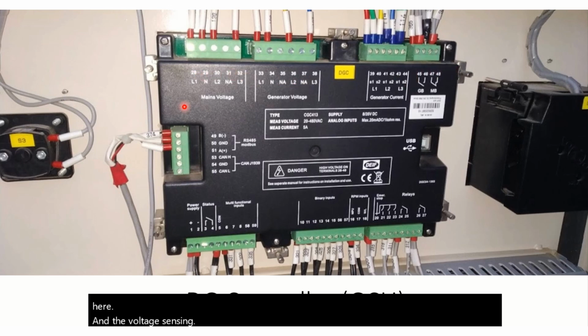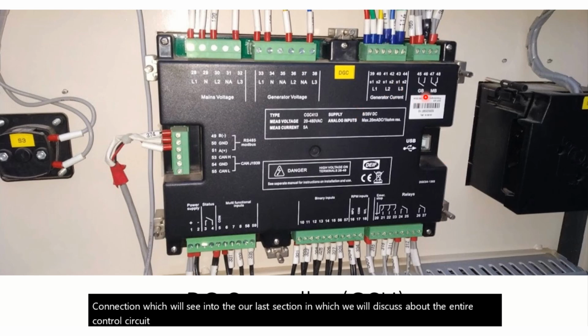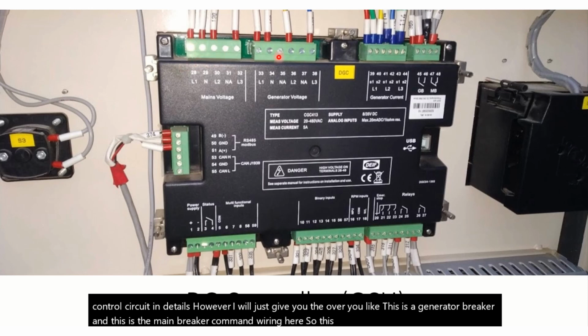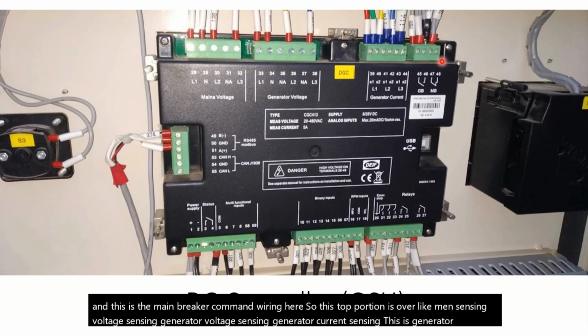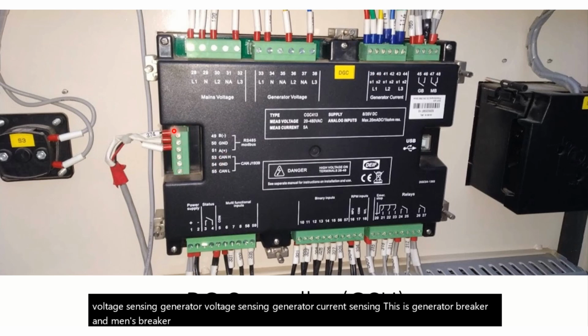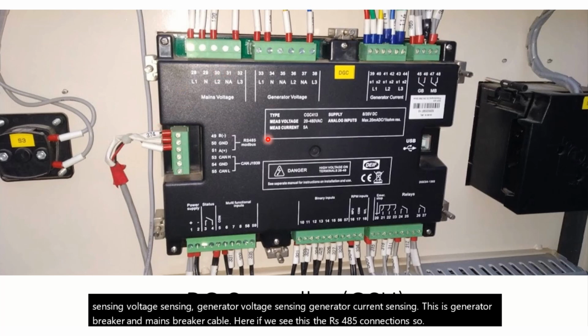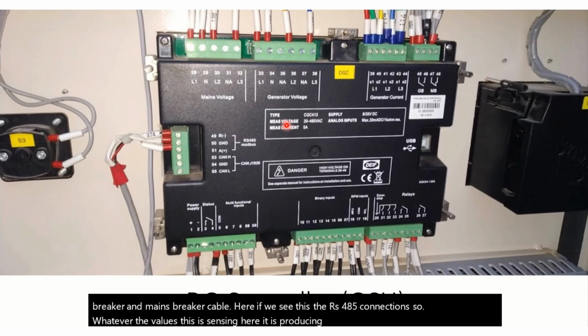These are all different connections which we will see in our last section, in which we will discuss the entire control circuit in detail. However, I will just give you the overview. This is the generator breaker and this is the mains breaker command wiring. So this top portion is mains voltage sensing, generator voltage sensing, and generator current sensing. This is the generator breaker and mains breaker cable. Here we see the RS485 connections. Whatever values it is sensing, it shows on the display we saw in the previous slide.